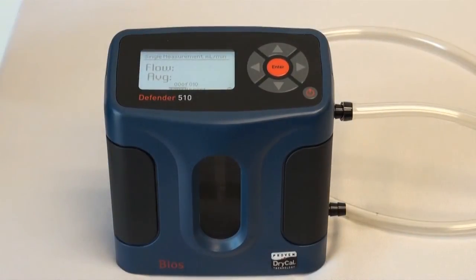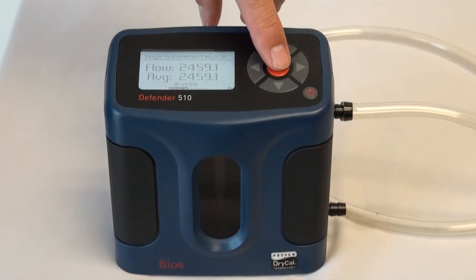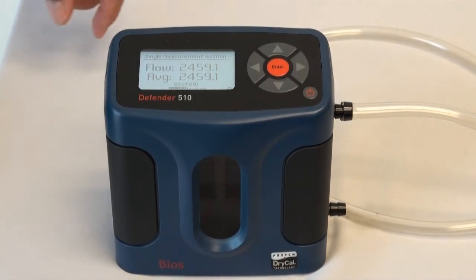As with the DryCal, take an average of six to seven readings and adjust the Escort Elf flow rate according to your average reading.